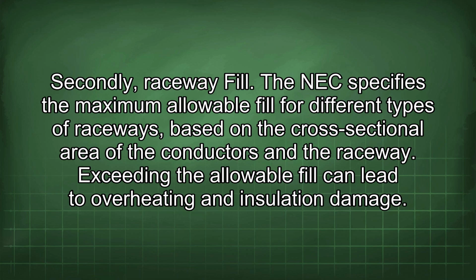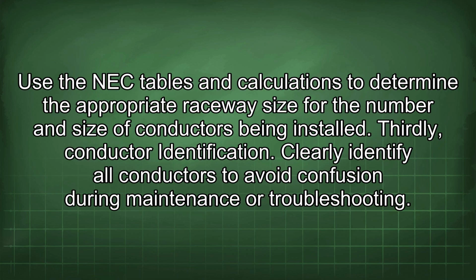Secondly, raceway fill. The NEC specifies the maximum allowable fill for different types of raceways based on the cross-sectional area of the conductors and the raceway. Exceeding the allowable fill can lead to overheating and insulation damage. Use the NEC tables and calculations to determine the appropriate raceway size for the number and size of conductors being installed.